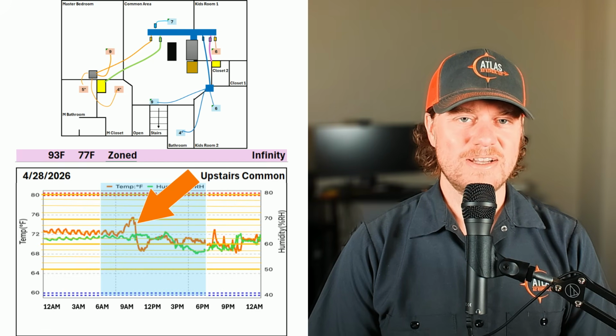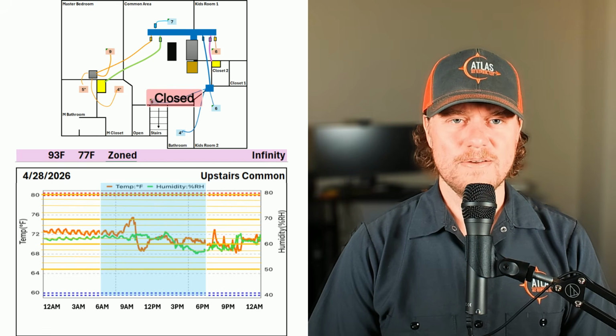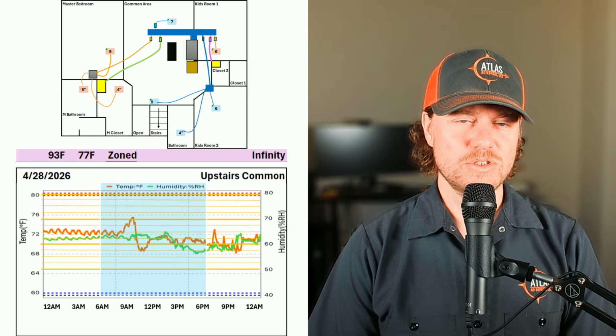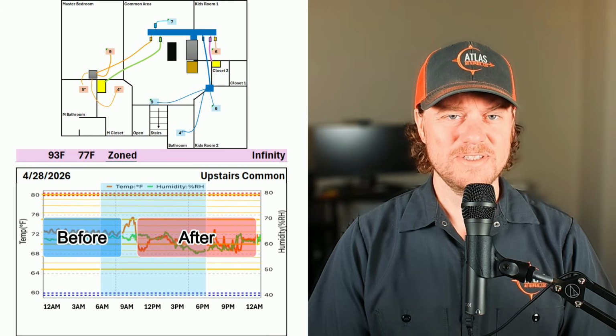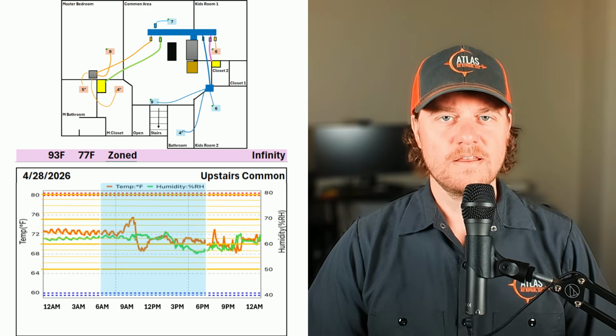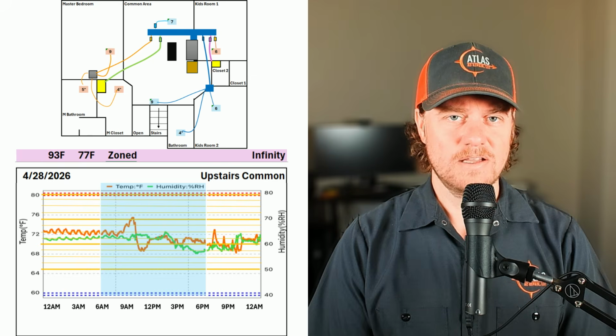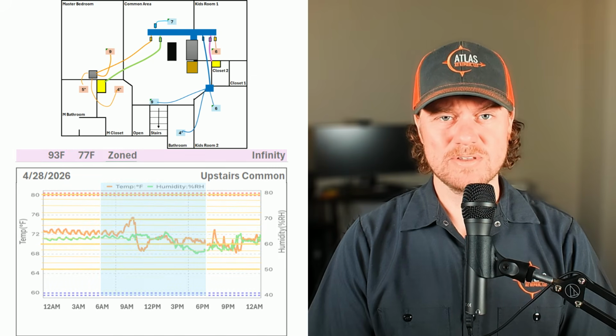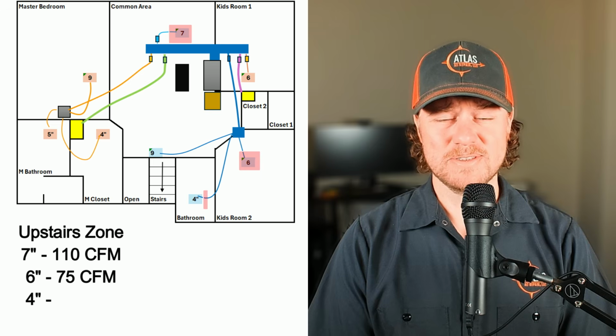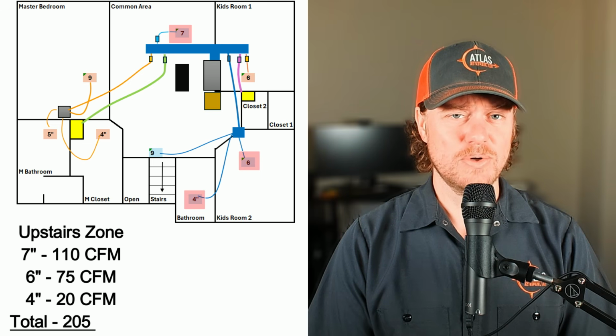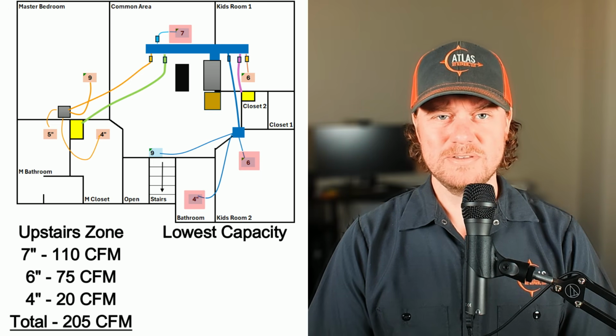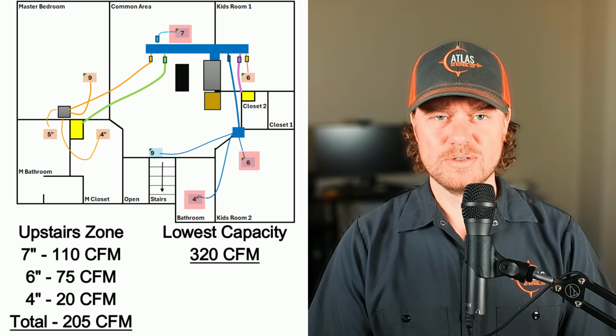I then went to the 9-inch duct above the stairwell, closed off the vent completely in order to artificially create high static pressure. And you can see how the system is kind of freaking out a little. The temperature lines are now harsh and erratic. The reason for this is the only ductwork that's left on the zone is a 7-inch, a 6, and a 4, which only gives us 205 CFM. And at the lowest speed, this system operates closer to 320 CFM.